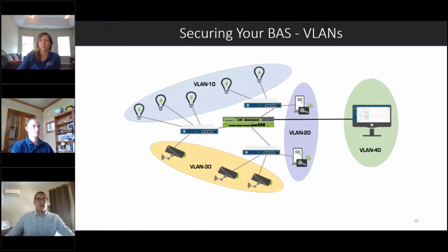You're segmenting the communication traffic between those networks, but they're still able to be connected back to the same Ethernet switch. So that's a helpful setup. It allows for a lot easier troubleshooting. You're going to understand where the communication traffic is going with these different VLAN networks. Best practice, it's not a hard rule, but it's something to try to stick to, is no more than 250 devices per VLAN. That helps you with understanding traffic flow and really optimizing your system performance.